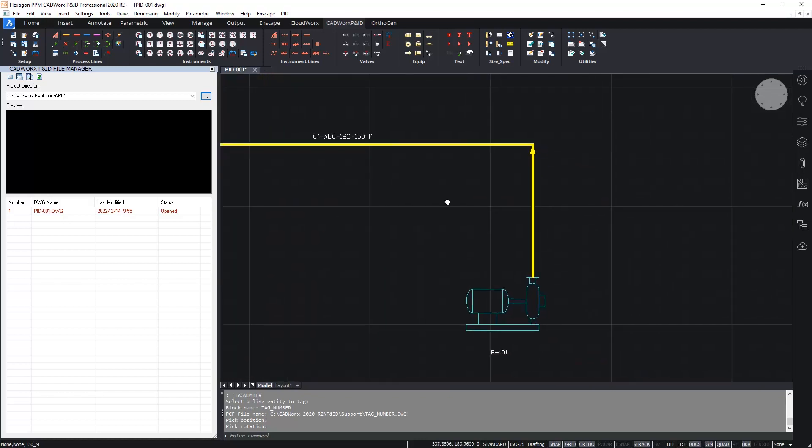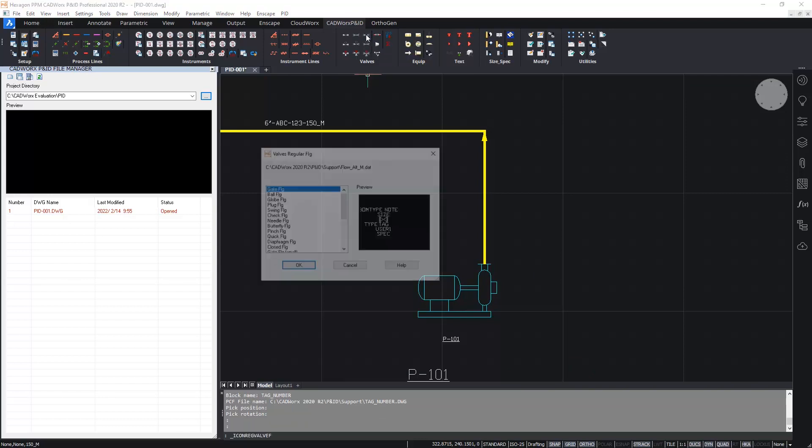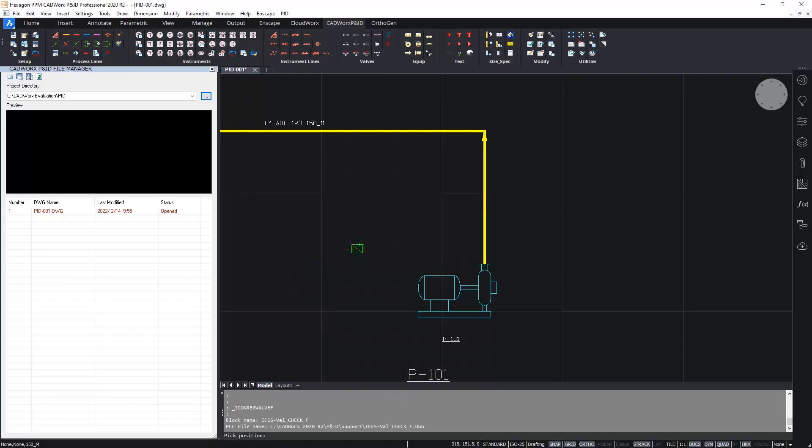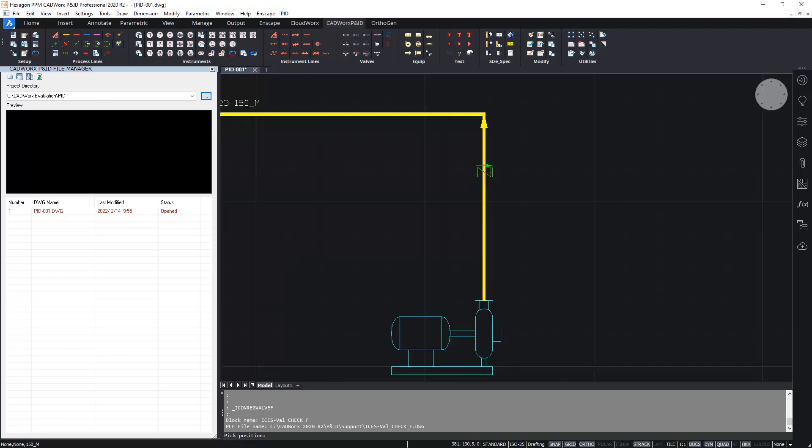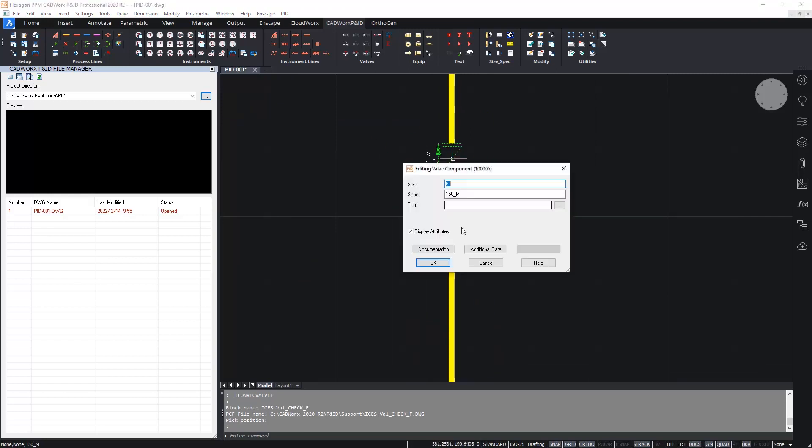Okay, let's add some inline items now. I'm going to add a flanged valve here. So I'm going to pick from the flanged valve icons. And on the pump discharge line, as is typical, let's insert a check valve, a flanged check valve from the symbols library. Insert that, again, attach it onto the line. As you can see, the line is automatically trimmed back to fit the flanged valve in. And I will finish this off by just giving this a tag CK1.